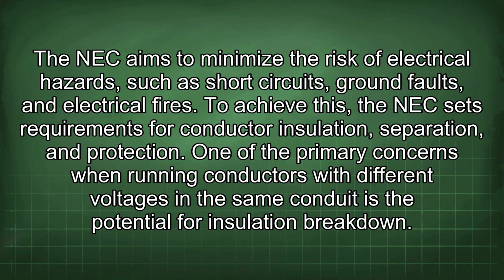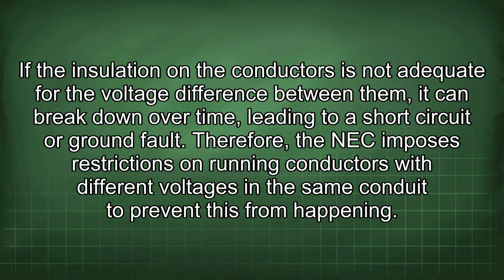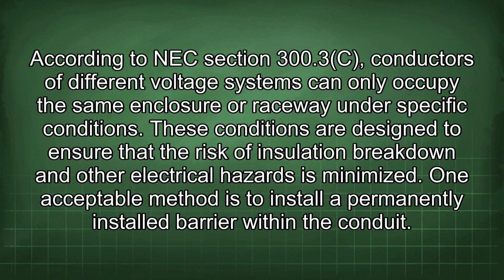One of the primary concerns when running conductors with different voltages in the same conduit is the potential for insulation breakdown. If the insulation on the conductors is not adequate for the voltage difference between them, it can break down over time, leading to a short circuit or ground fault. Therefore, the NEC imposes restrictions on running conductors with different voltages in the same conduit to prevent this from happening. According to NEC section 300.3(C), conductors of different voltage systems can only occupy the same enclosure or raceway under specific conditions. These conditions are designed to ensure that the risk of insulation breakdown and other electrical hazards is minimized.